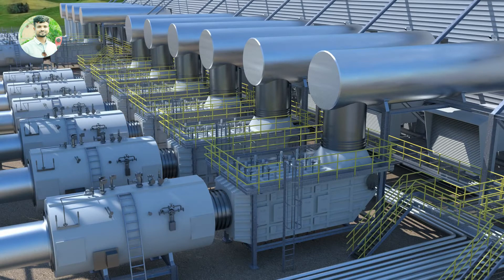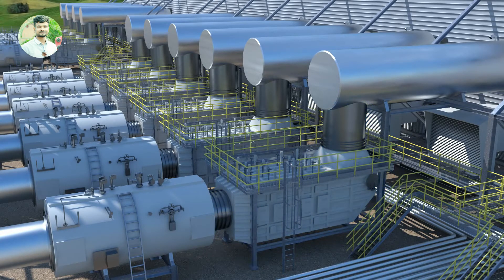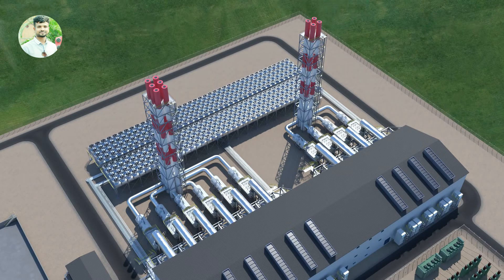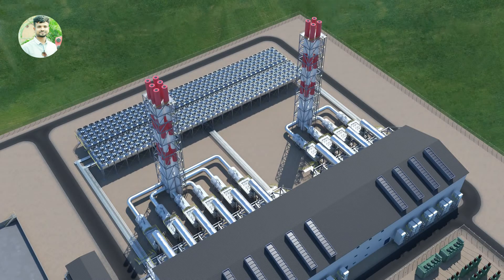With the standardized denoxification system, the amount of environmentally harmful nitrogen oxide from the flue gas is reduced through selective catalytic reduction down to the respective regionally valid air pollution emission limit values. The layout of the plant has been designed to be adjustable for various waste heat recovery systems.